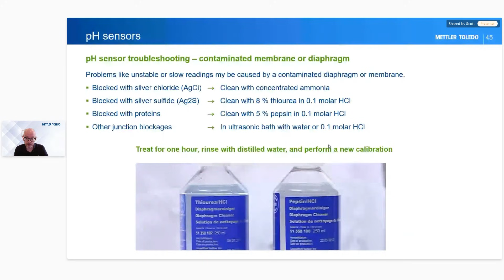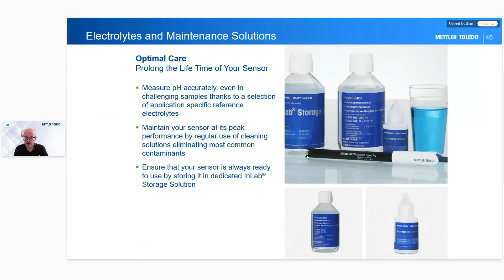Okay, once we've done this and treated an electrode, we must rinse, clean, and then perform a new calibration. So yet again, anything we do to clean the electrode, we must perform a calibration afterwards to make sure. For the lifetime of the sensor, obviously, yet again, we do storage solutions, we do pepsin solutions, all those different things to try and keep it ready. So there are things you can look at in the Fisher catalogue, and it's full of solutions there that you can use as well to keep your electrode in the best condition.